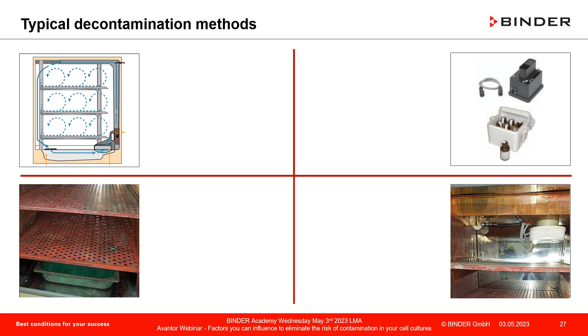Right here we have that 180 degrees C plus the HEPA filter. Personally, I'm not a fan of HEPA filter because, as you know, it's collecting contaminants in the vicinity and needs to be exchanged every 6 months. Plastic compounds frequently have rougher surfaces than stainless steel, and they contribute basically also to a large surface. If you go to the upper right-hand side, that's what a H2O2 vaporization set looks like.